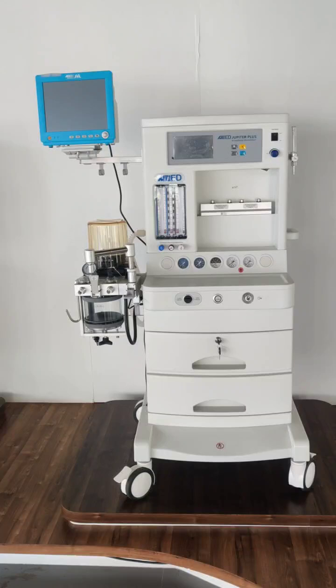So we have a central pipeline system at the back side of the machine, and we are giving 2 yokes, one for oxygen for mounting the cylinders and one for nitrous oxide for mounting the nitrous oxide cylinders. Both of these yokes are the pin index yokes.